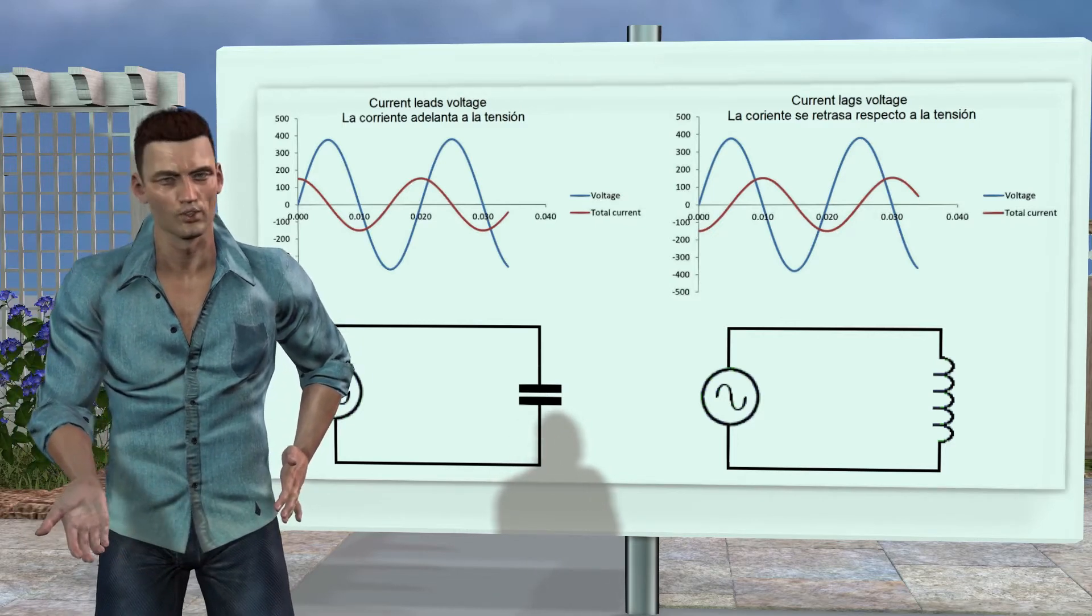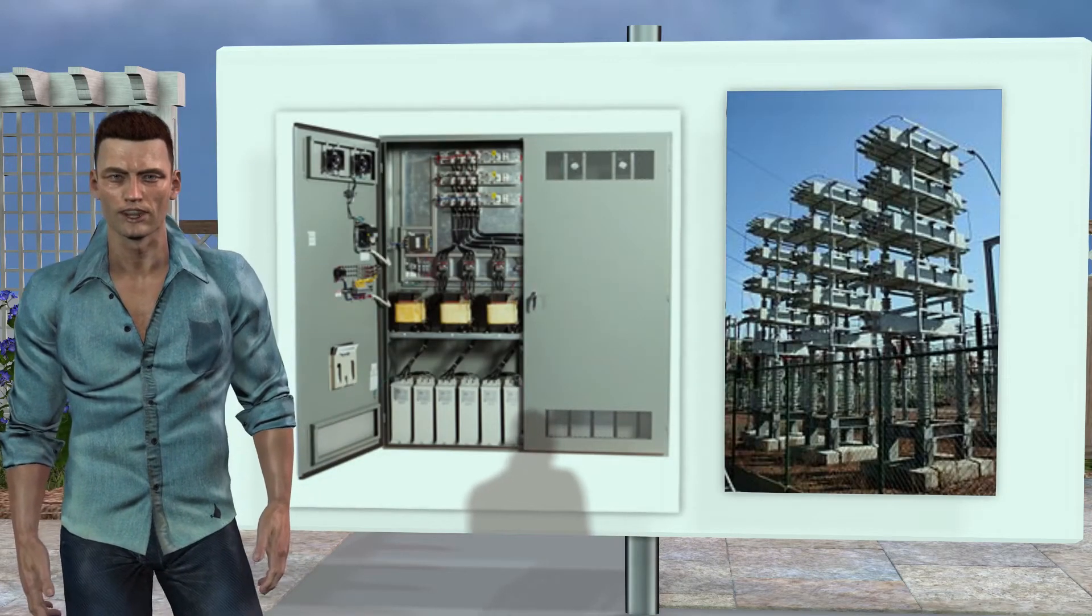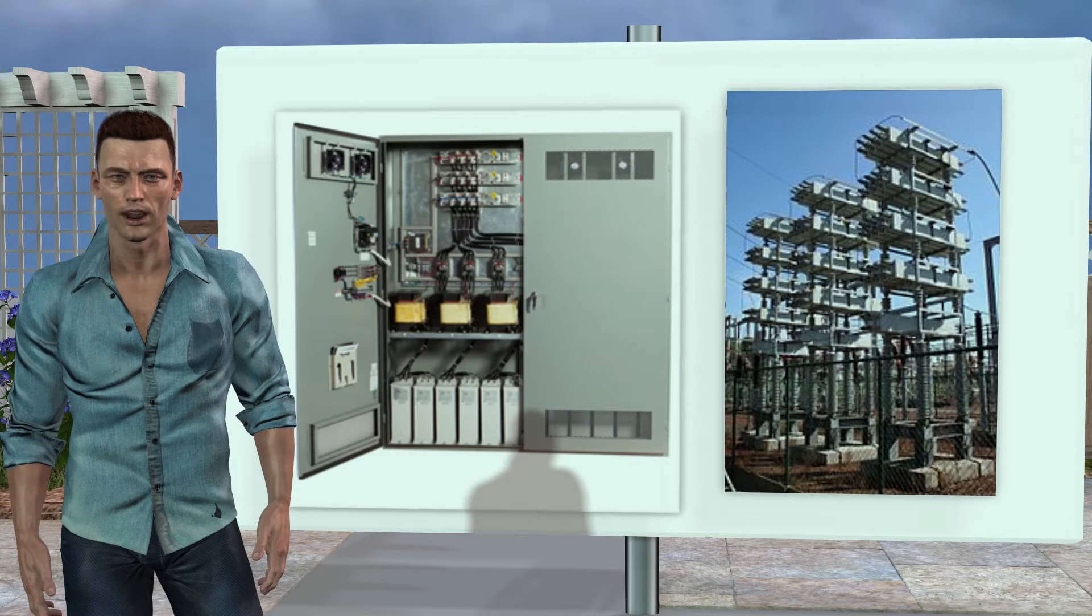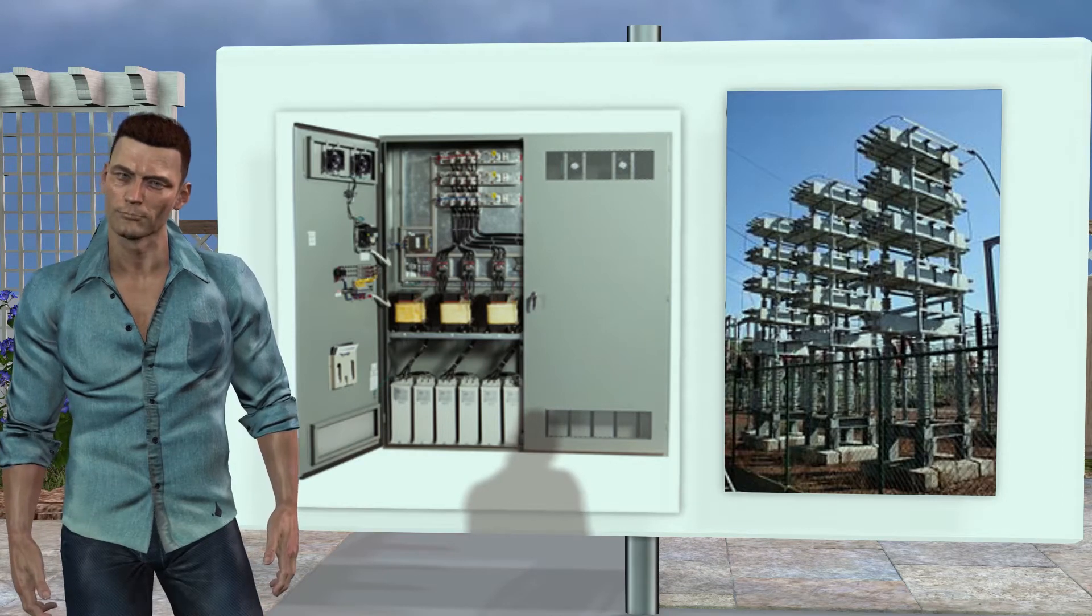This means that coils and capacitors give rise to opposite phase shifts, this being the basis for using capacitor banks in installations with many motors, in order to compensate for the inductive reactive power generated by motors in the installation.